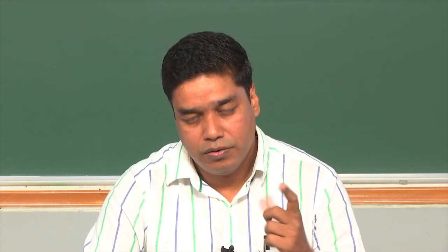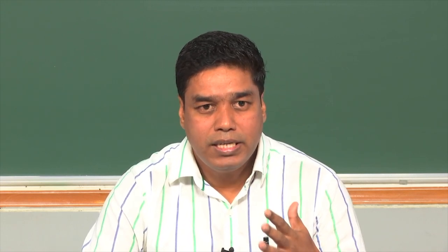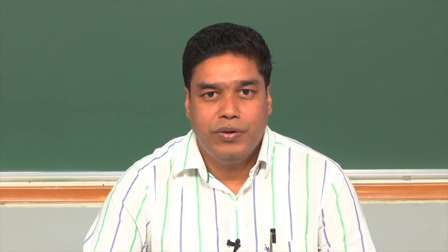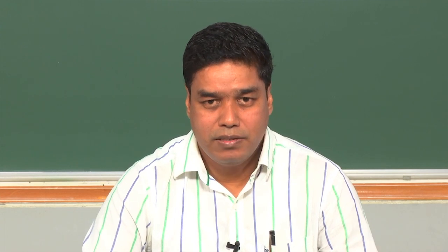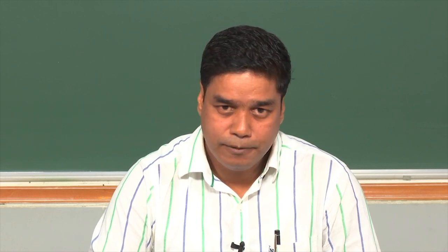By doing calibration you not only get error-free results, but also information about the location of the defect and some idea about its size. Ultrasonic testing in that sense provides quantitative information as well, although it is primarily a qualitative test. Through this kind of calibration and calculation you can get the depth at which defects are located and an estimate of flaw size.